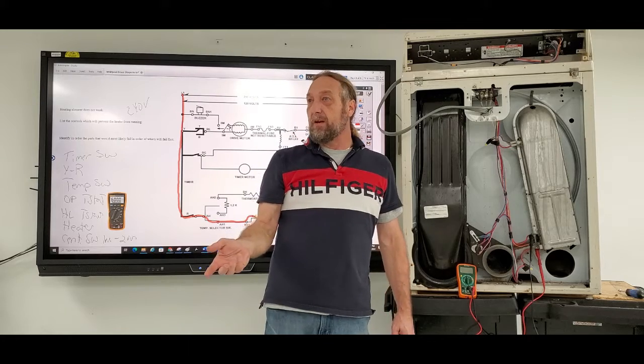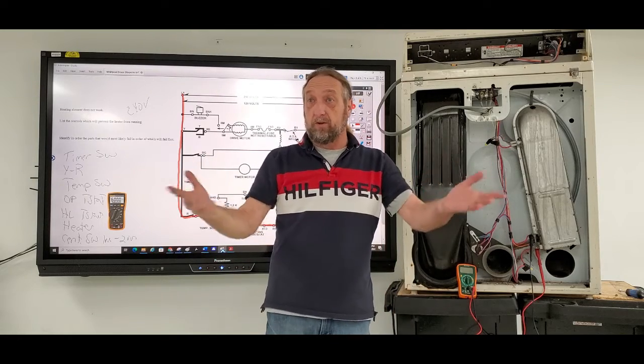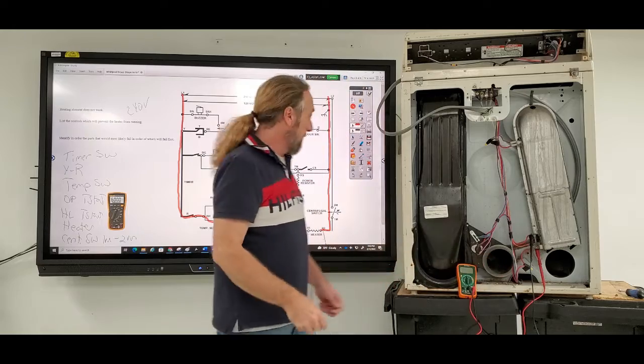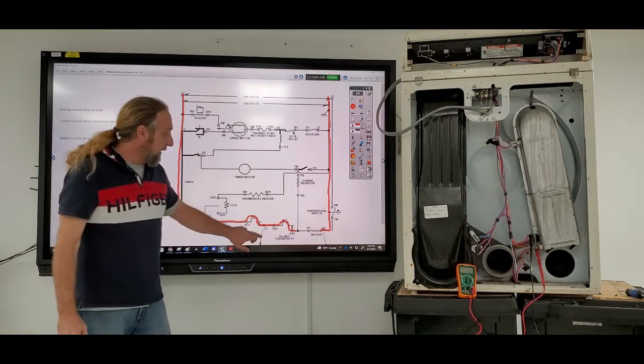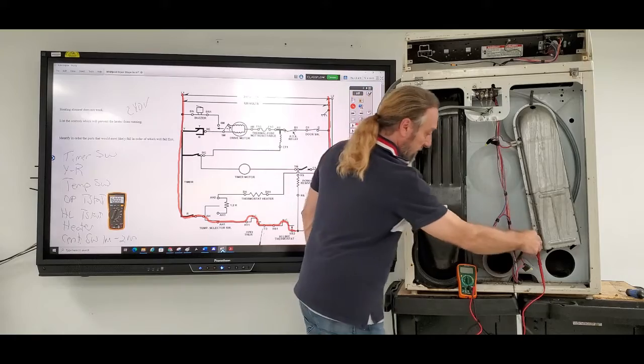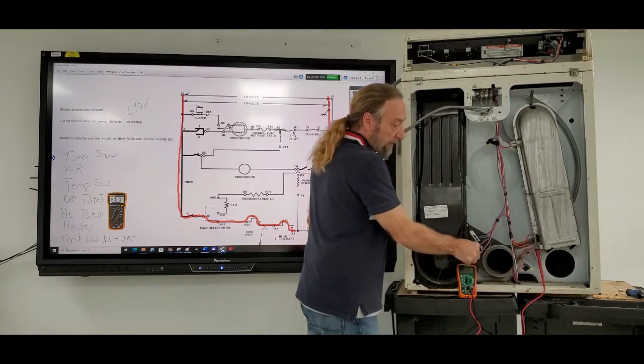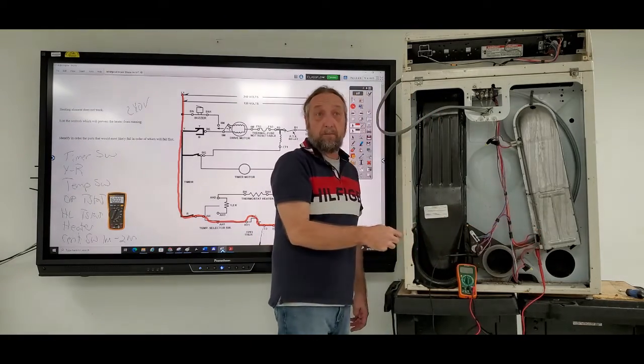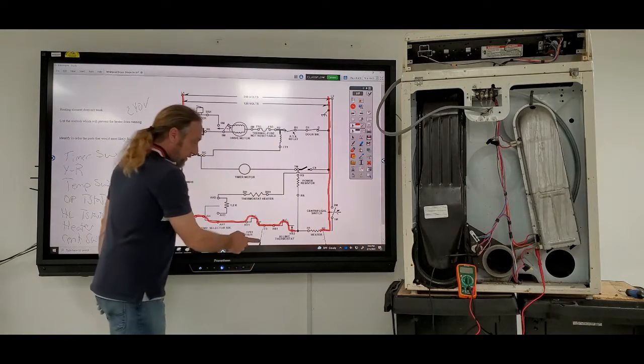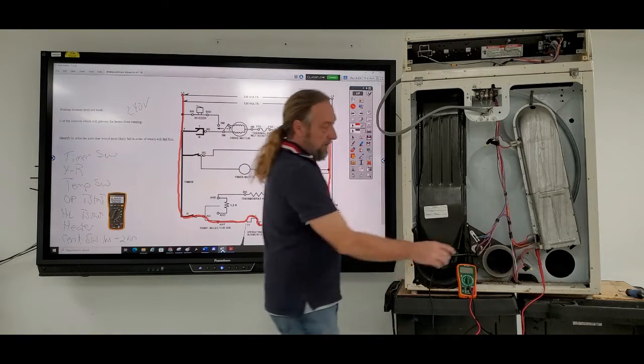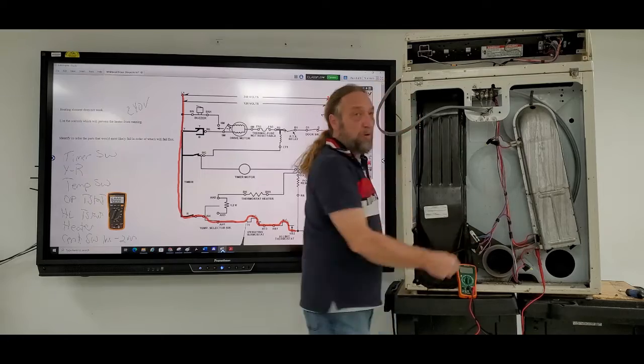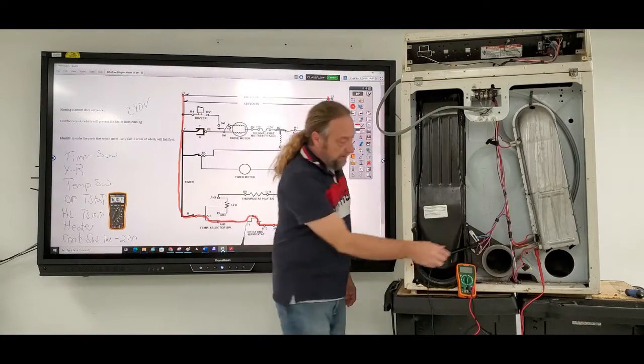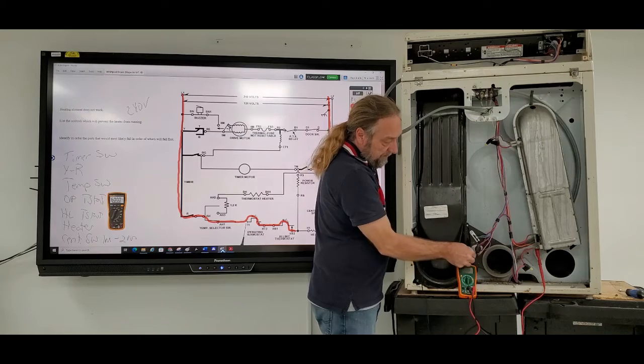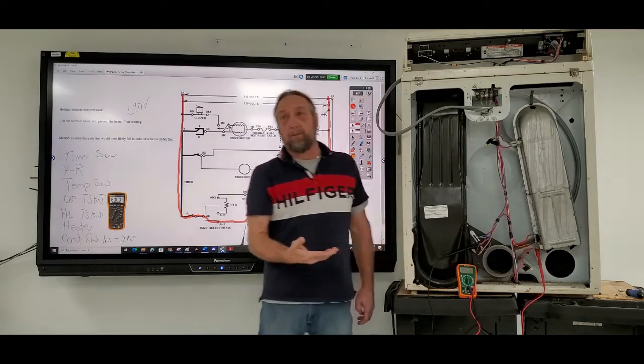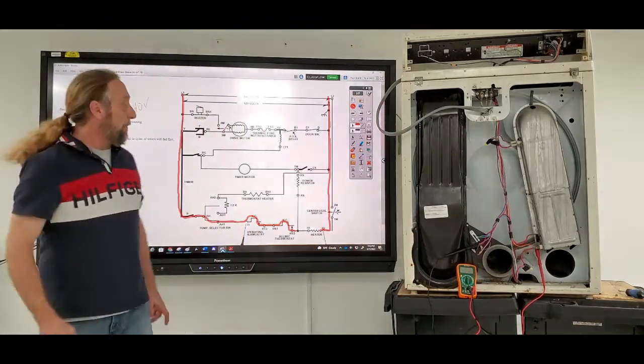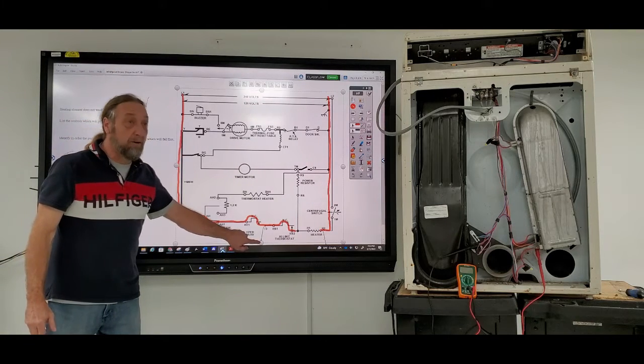If I had voltage there, the wire is broken between the two parts. If I don't, I go to the other side of the thermostat. If I don't have voltage, now I go to this thermostat, the operating thermostat, and I go here. I don't have voltage, well there's a wire from one to the other. I go to the other side of the thermostat, here. Oh, I have voltage. I didn't have it here, I have it here. What's my problem? The operating thermostat.